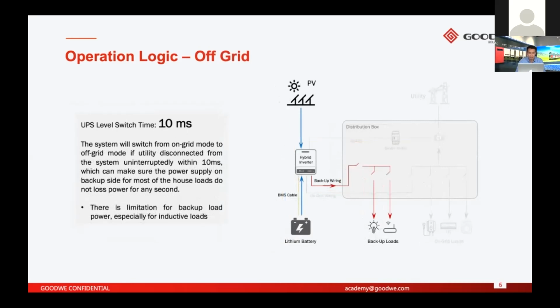For hybrid systems, one of the most important features is they can work without grid. It means they work in off-grid mode. If the grid fails during operation, the switch from on-grid mode to off-grid mode has a UPS-level switch time of less than 10 milliseconds. So most of the house loads, if they are in use when the grid is normal and then suddenly the grid shuts down, the whole system will switch to off-grid supply, and most of the loads will not stop. It's continuous power supply. This is a difference from EPS.